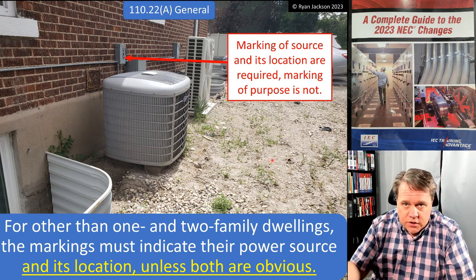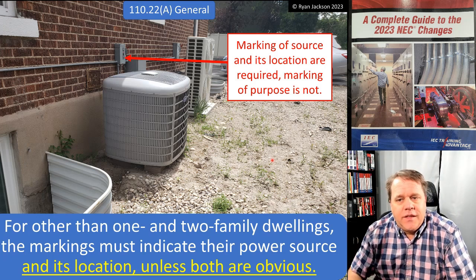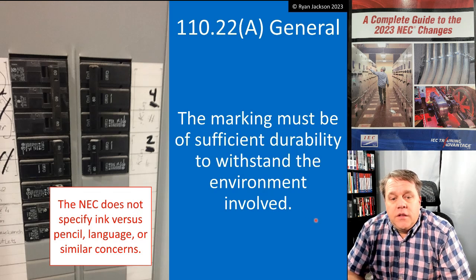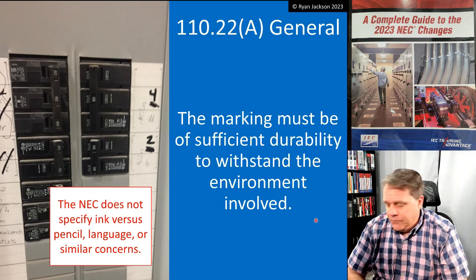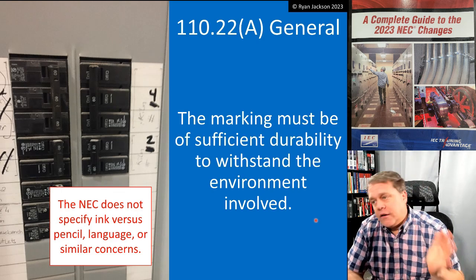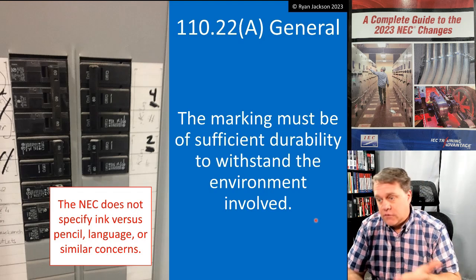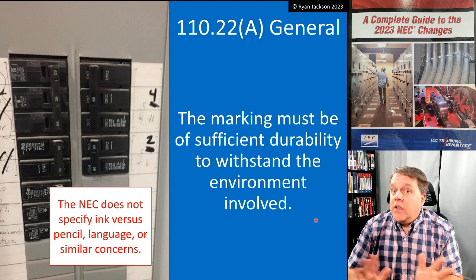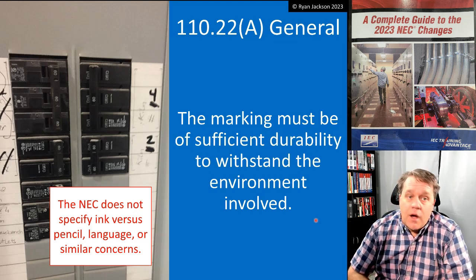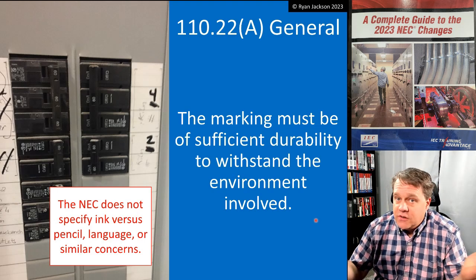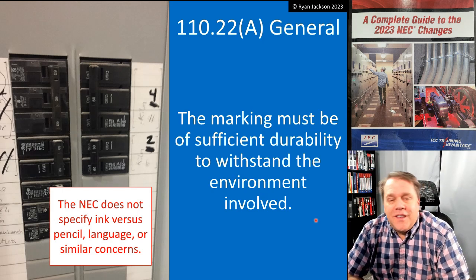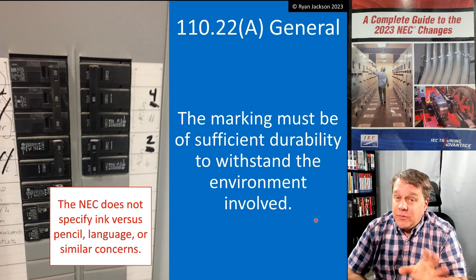The marking must be of sufficient durability to withstand the environment involved. The NEC doesn't specify whether it needs to be in pencil or ink, or what language it must be in - that's left up to the authority having jurisdiction. There may be instances where pencil or pen is preferred, or where different languages are required depending on the facility and the people involved. So there you go - 110.22. I think they did some good work in that section.